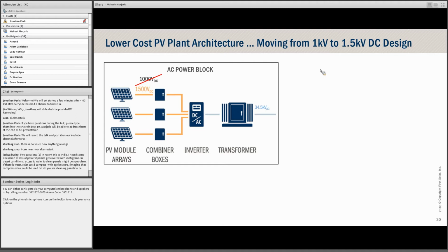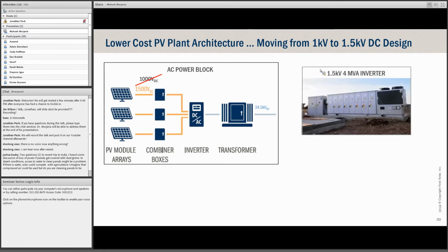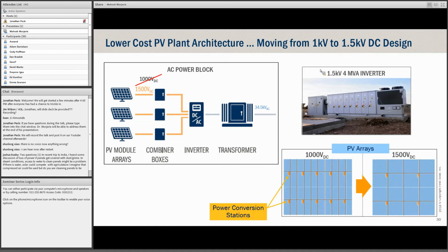Why 1000 volt? Well, the higher the voltage you go, you have less losses, you can build into larger plants, etc. So we started building at 1500 volt DC instead of 1000 volt, and developed, almost 4 or 5 years back, with GE, a very large inverter - a 4 MVA inverter at 1500 volt DC.